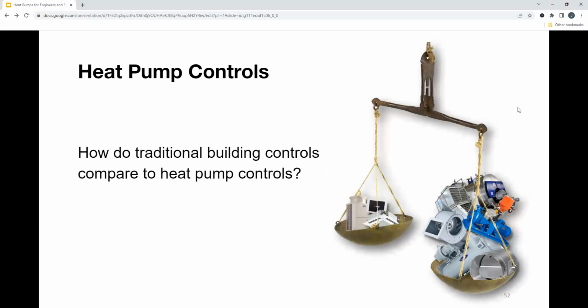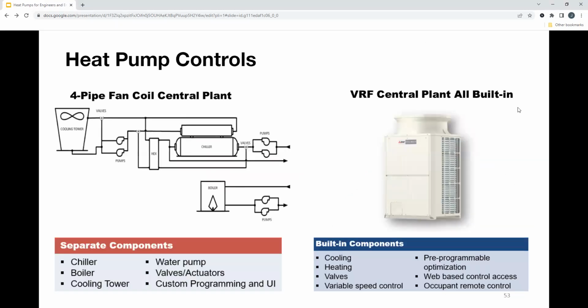So heat pump controls. We don't typically talk about this a lot. We typically just talk about the equipment itself, but controls is a huge aspect to the operation of this equipment. So how do traditional building controls compare to heat pump controls? All right, so if you take a look at this, central plants are huge and expensive. Typically, you'll have cooling towers, chillers, pumps, frequency drives, boilers, even more pumps, valves, controls, pressure transducers, really everything. There's a lot going on in a 4-pipe fan coil central system here, right?